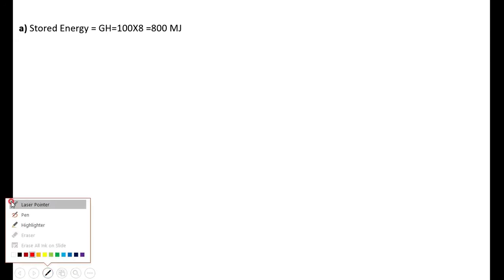First, we will find out the stored energy. The equation is: stored energy equals S times H, or H equals stored energy divided by S. That is, the inertia constant is the ratio of stored energy to S. The stored energy equals S times H. Therefore, with S equal to 100 and H equal to 8, the stored energy is 800 MJ.